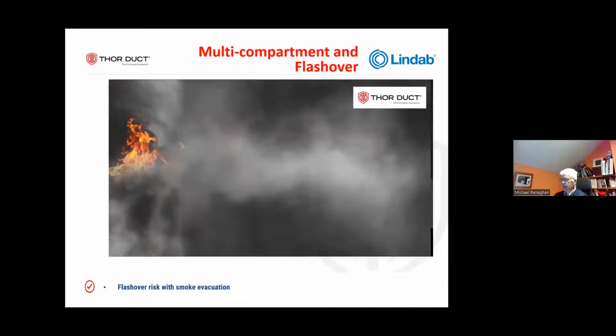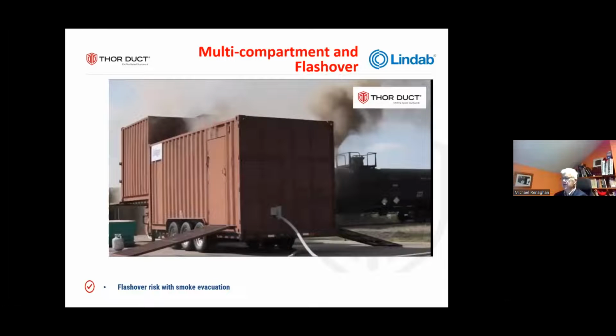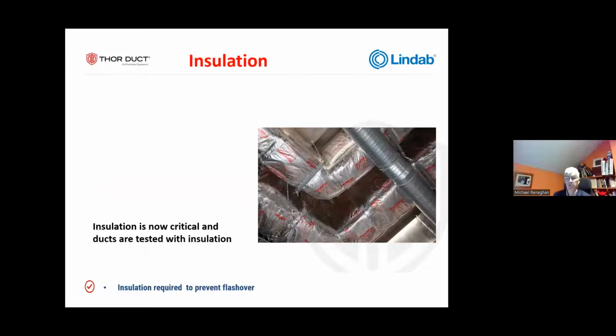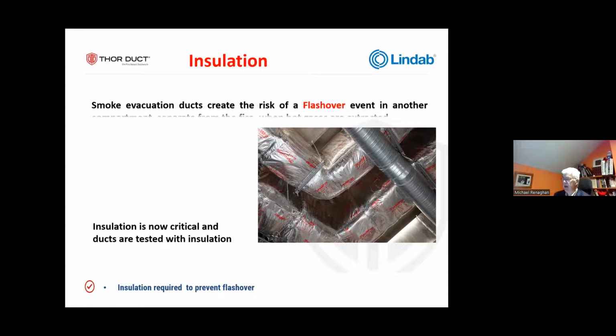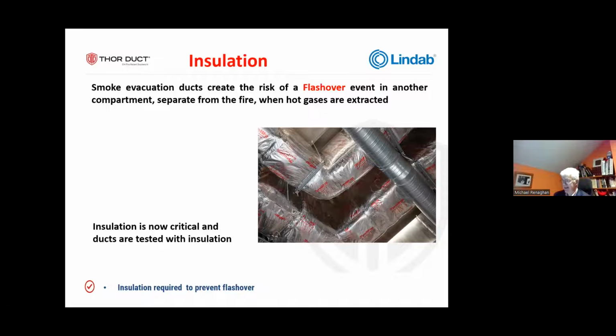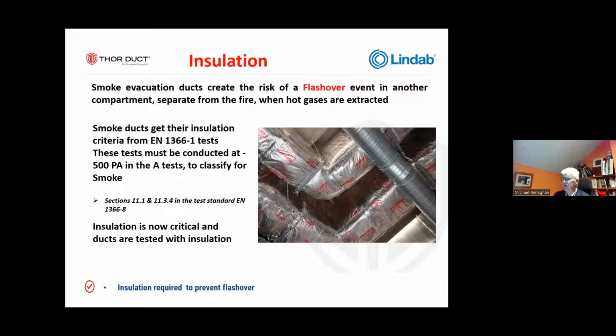Okay, so we are aware then that flashover is a real concern for us in terms of removing smoke, because ultimately we don't want the fire breaking out in other areas of the building or behind the firefighting crew. So all multi-compartment smoke extract ducts are insulated, and they're insulated to keep the heat on the inside, not on the outside. Okay, so that's part and parcel of the testing. You will see insulation in a lot of places now as a requirement for multi-compartment smoke extract.